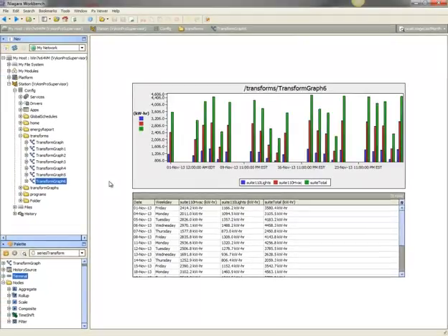Transform graphs serve as templates to define data sources and to configure graph nodes which manipulate the data for reporting purposes. The data manipulation includes combining data sources into single data sets using the composite node and applying functions to the data using the aggregate, rollup, and scale nodes. The addition of the time shift node facilitates comparing data from different time ranges, such as making year-over-year or month-over-month comparisons, while the filter node allows injecting a predicate into the query, which facilitates more robust exception-based reporting.